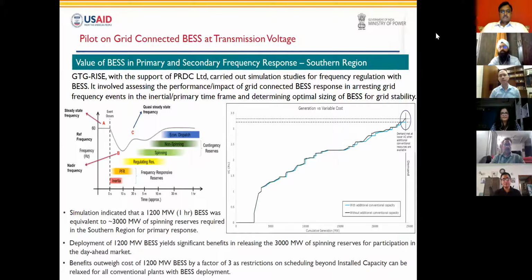Now there's another component of the transmission-level battery energy storage system which we modeled, for the southern grid. This was essentially a simulation study we carried out along with PRDC, our partner on the simulation studies. What we wanted to find out is the contribution of battery from the perspective of frequency management, both primary and secondary, and how battery would play a role in a real-time environment. So we modeled the system, simulated the southern grid in its entirety, and looked at primary and secondary frequency contribution of batteries of various capacities. We found that about 1,200 megawatts of battery would effectively replace the 3,000 megawatts of spinning reserves currently required — and we hold this out, by the way, in the Indian system.